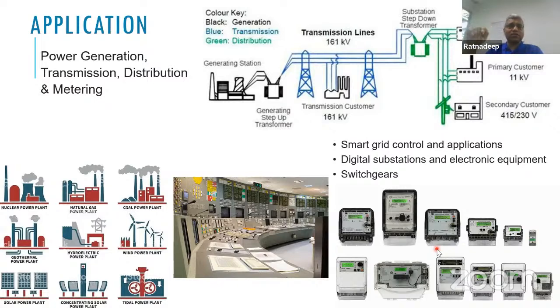And there is accuracy around it - getting slightly deeper, accuracy is called in terms of class: class 1, class 2, class 0.5, class 0.1, class 0.01. Normally in our houses, we have meters which are class 1 meters. Class 1 means it is accurate to 1% of whatever you are measuring.